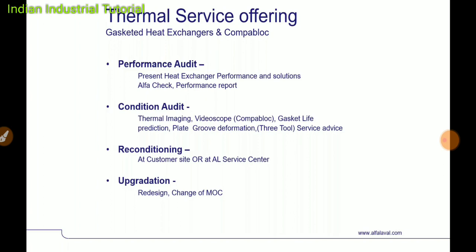Reconditioning: at the Alfa Laval Service Center, we offer entire reconditioning, including groove repair, and pinhole and crack identification and removal of those plates. Upgradation: we offer redesign and change of the MOC. For example, if you have an SS316 plate having a corrosion problem all the time, we will analyze the chemical liquid you are using for heat transfer. Based on that, we suggest the right material of plate and we replace those plates under upgradation.